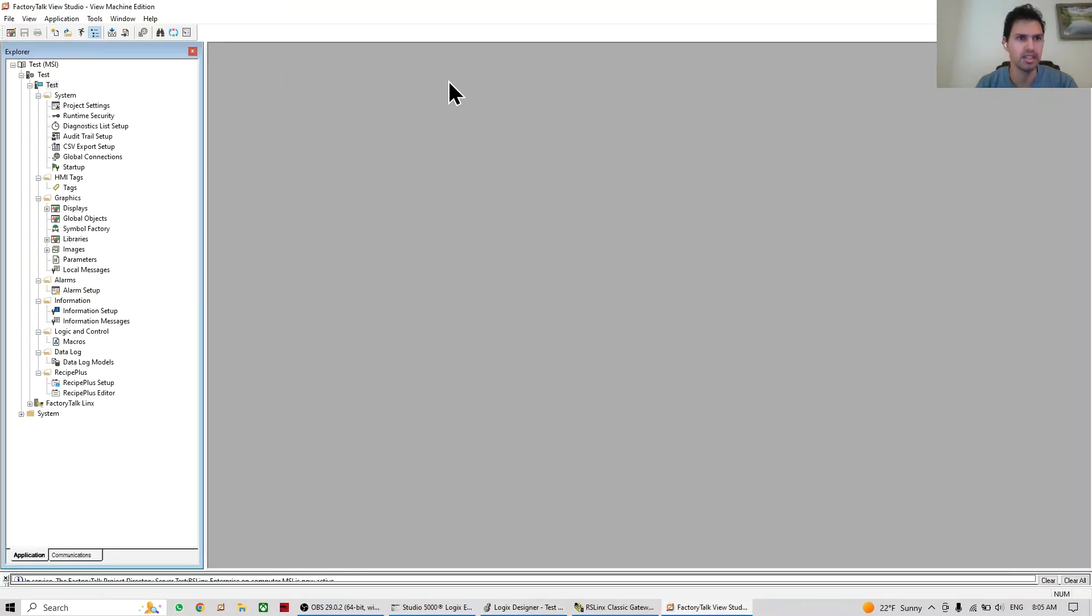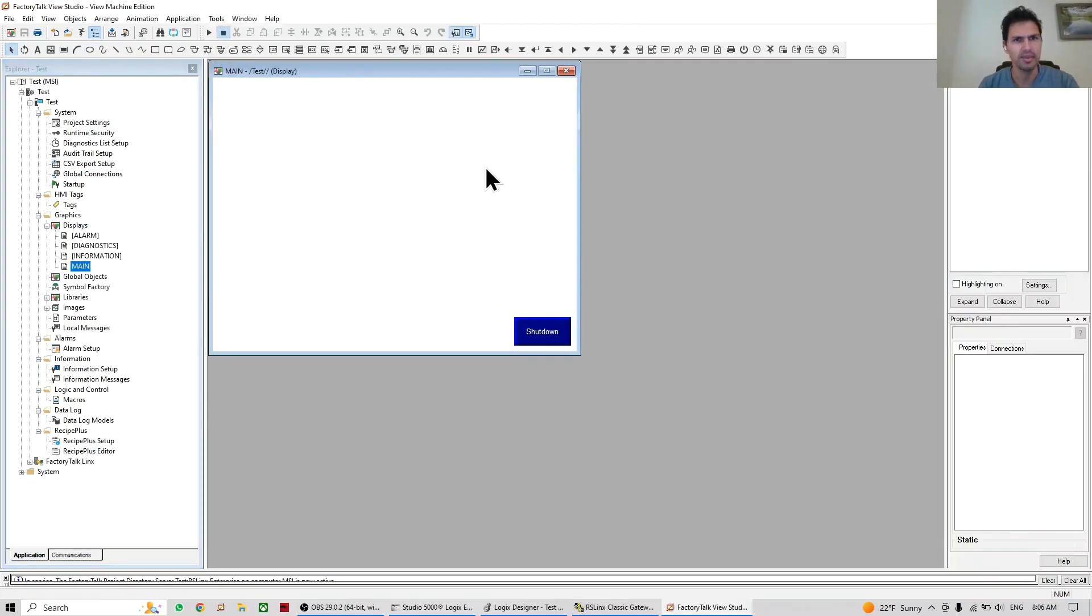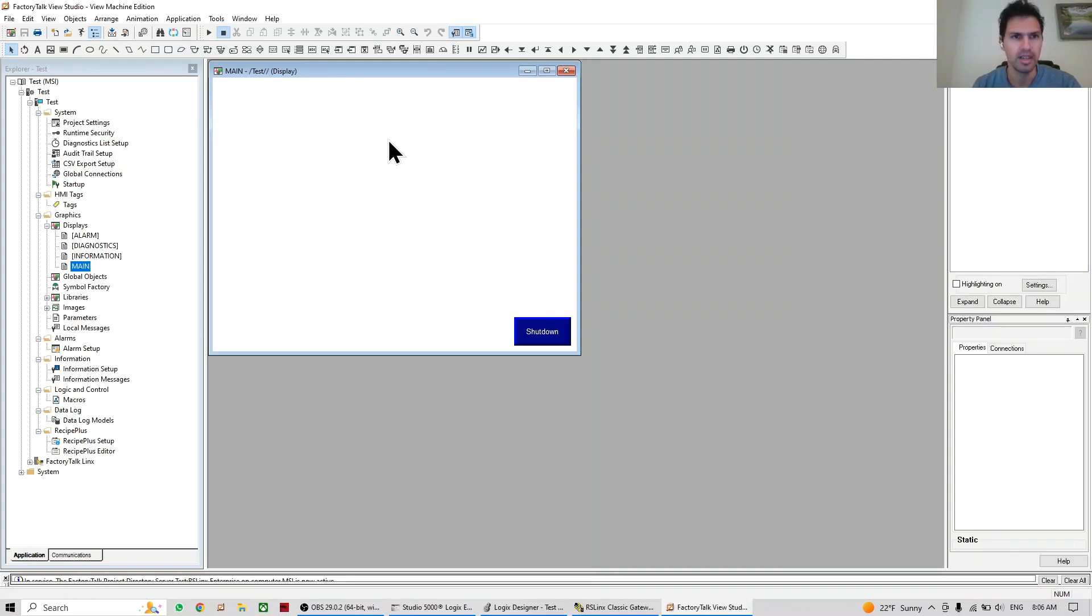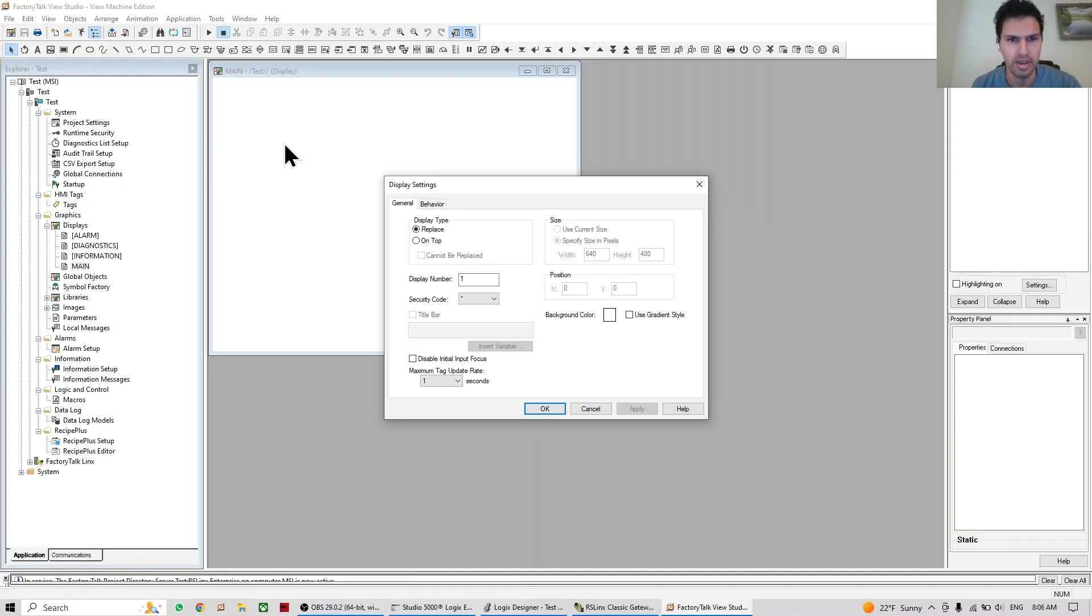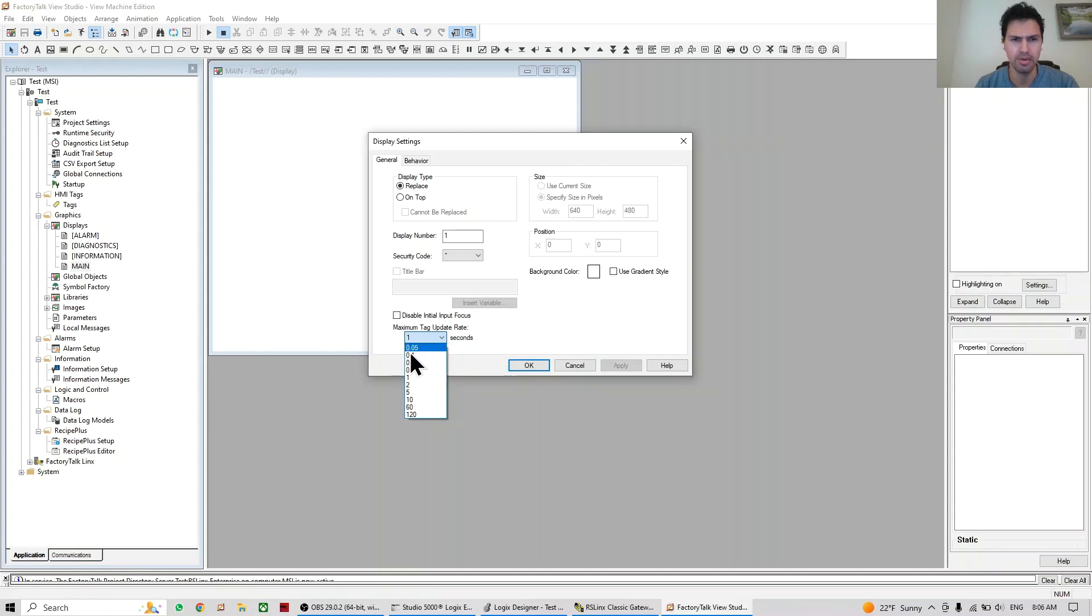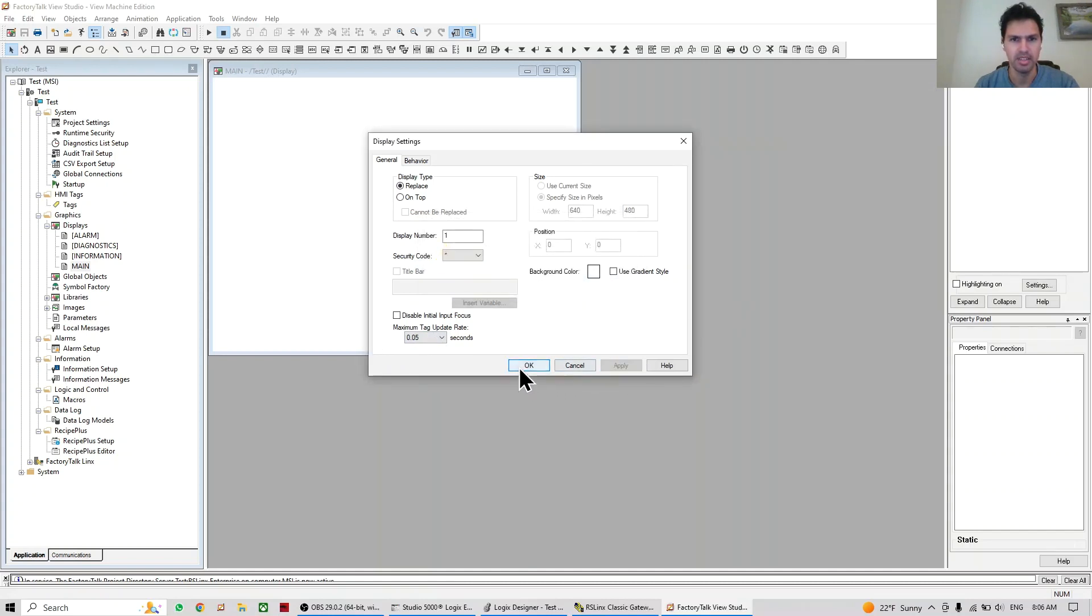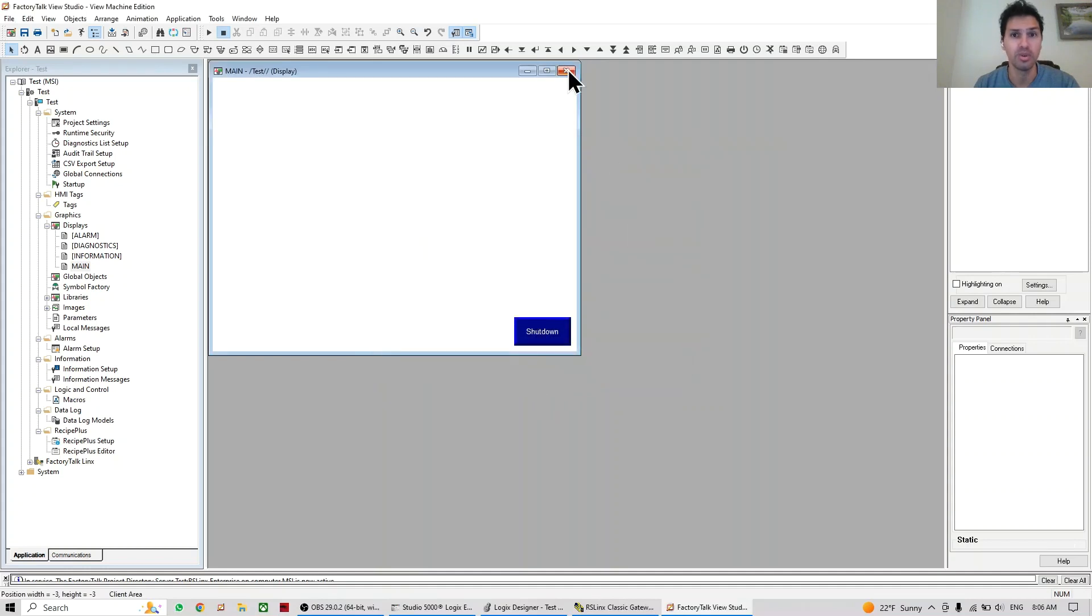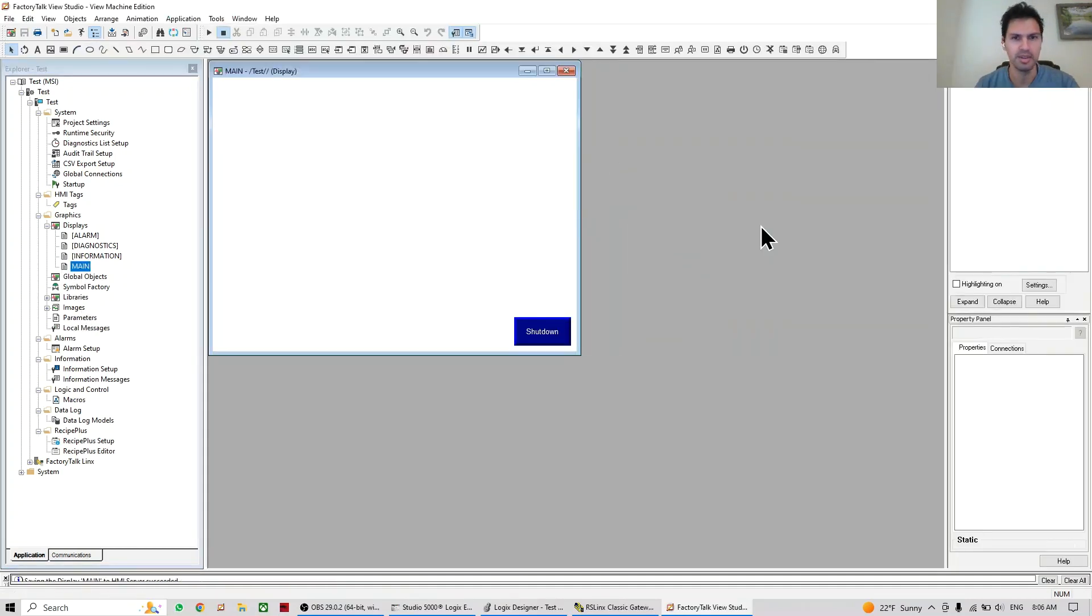So we come here, our new project is open, we go to display. The first thing I want you to do is whenever you're doing any animation, I recommend to right click display settings and go there for the update rate. This means how fast it's going to update the information from the PLC whenever you're doing the simulation. So here I'm going to select 0.05 since we're doing just a small program. We just need to do okay and close and open. I'm going to save menu and now we're going to start working.